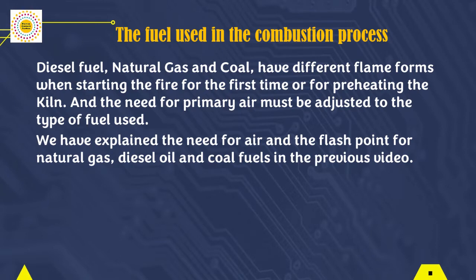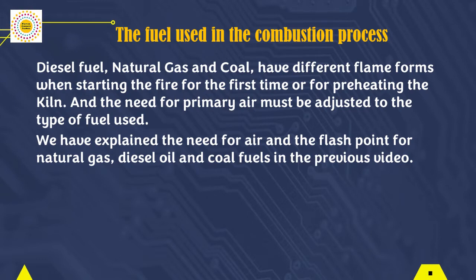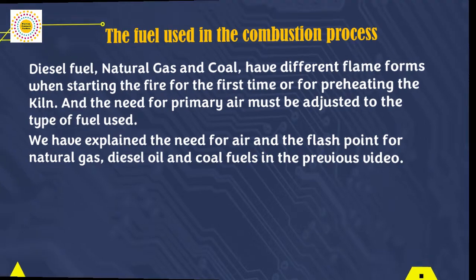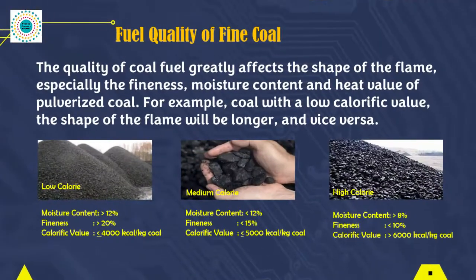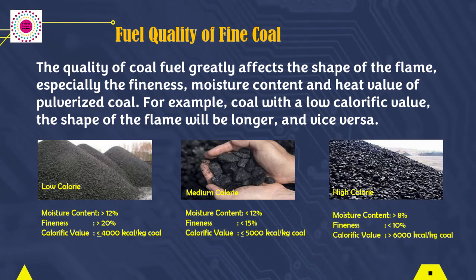The need for primary air must be adjusted to the type of fuel used. We have explained the need for air and the flash point for natural gas, diesel oil, and coal fuels in the previous video. The quality of coal fuel greatly affects the shape of the flame, especially the fineness, moisture content, and heat value of pulverized coal.